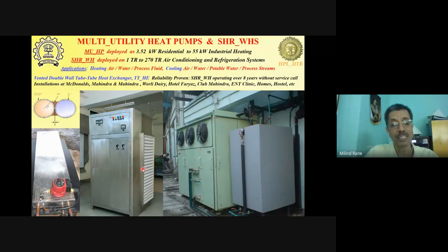So the shop floor air would get in from this side as well as a similar filter on the other side, and then there were two heat exchangers inside where the evaporator would cool and dehumidify the air, and then the air would be returned back into the indoor environment, thereby air conditioning the indoor space of a shop floor. And this recovered heat plus the compressor power to compress the refrigerant would then be delivered in the condenser to the solution which is being heated.